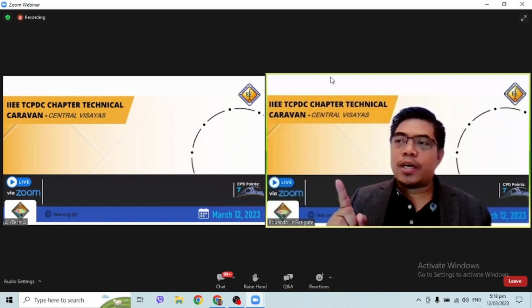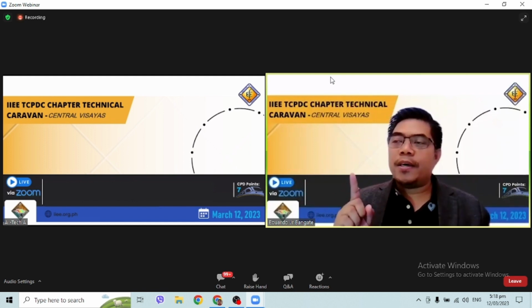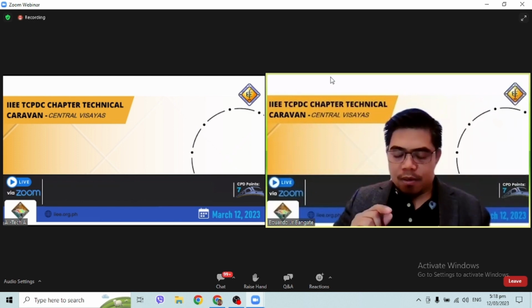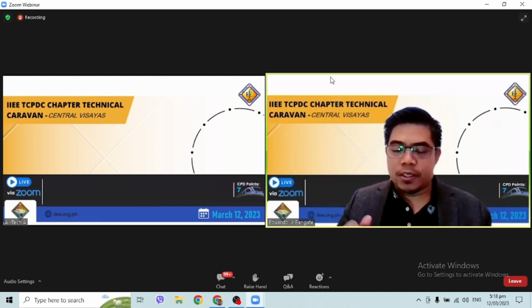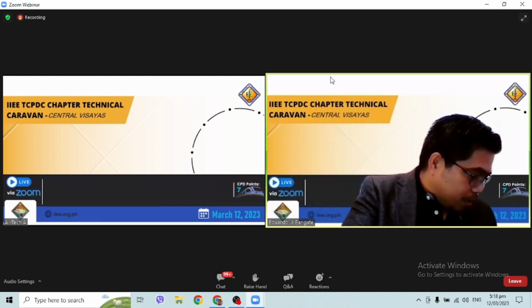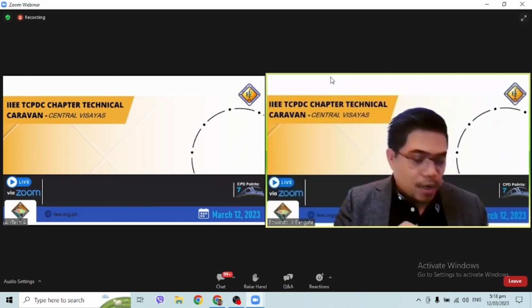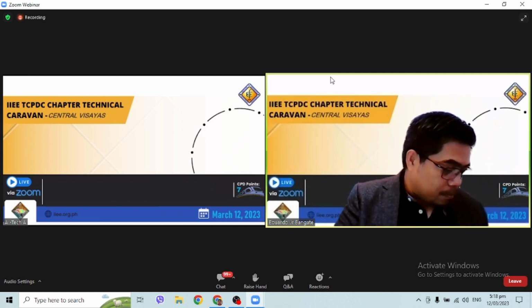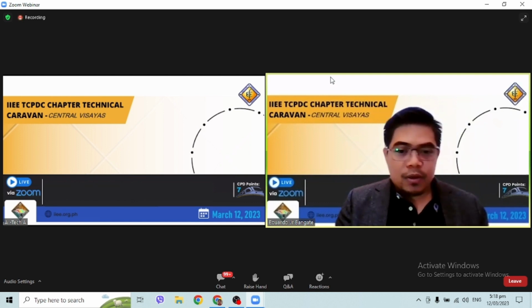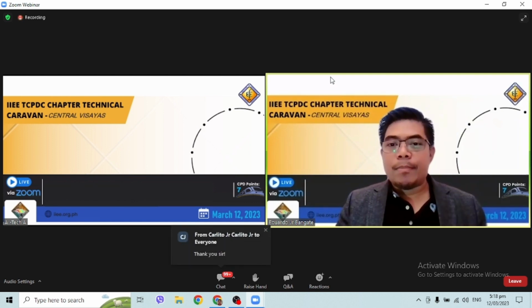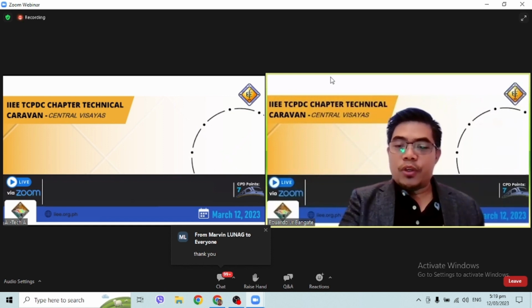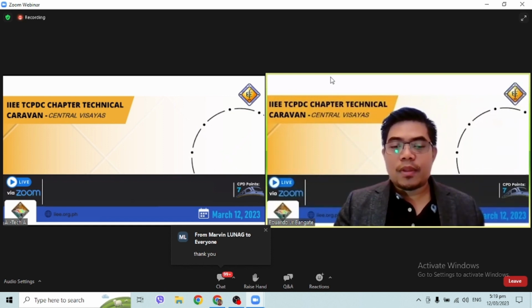Now, if you are saying that your load requires a generator that could handle higher harmonics, there is a high harmonics in the system, then use an excitation system like the PMG type. Okay, the PMG. So you will have a stable generator even when you put that type of load.